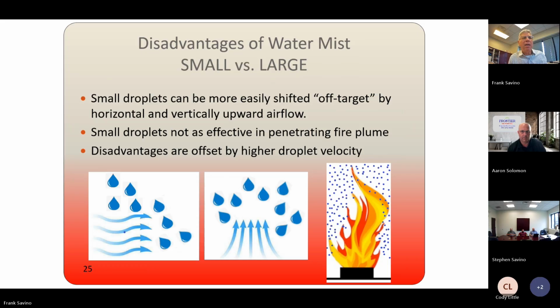What are your thoughts on areas where you've got hot aisle containment with big openings in the suspended ceiling, and you have to put sprinklers above and below the ceiling? Would you put mist above and below? Would you put pre-action sprinkler above and mist below? What is the thought behind that? Hey, Jeff? Is Jeff still with us? Yeah, I'm here. What is your thought on that, Jeff? If you're going to use it in the room, I would use it above the ceiling as well in that application.